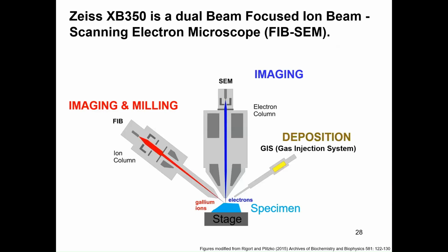This Crossbeam 350 is a dual beam focused ion beam SEM. In the center column is the electron column, which produces electrons, but we have another ion column, which produces gallium ions, and we have another device called the gas injection system to deposit platinum onto the samples.